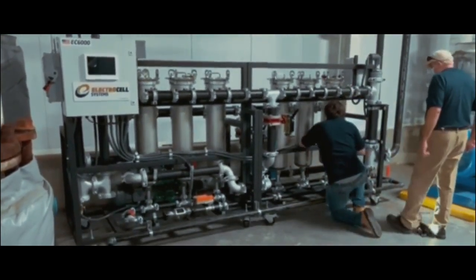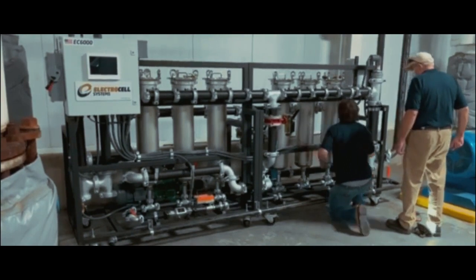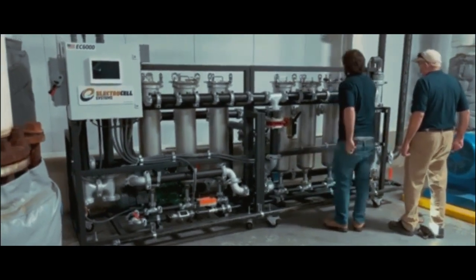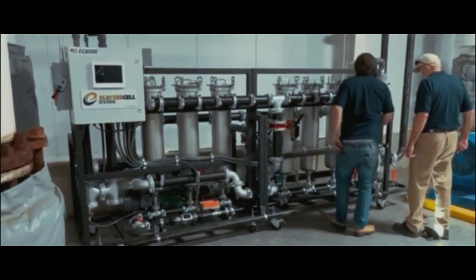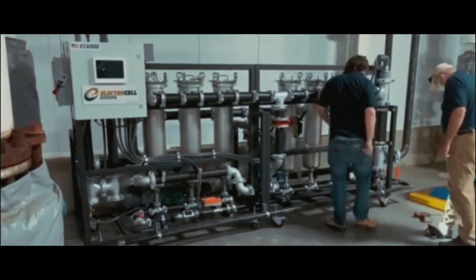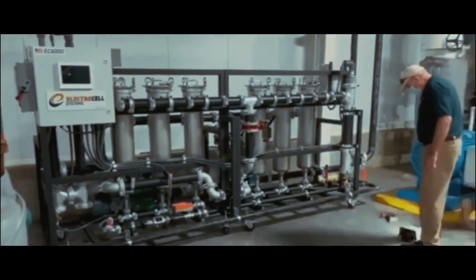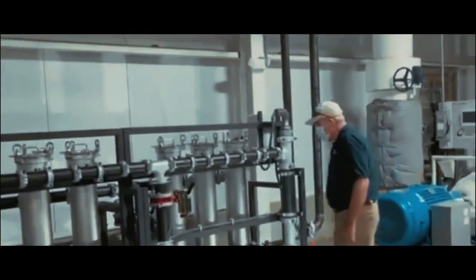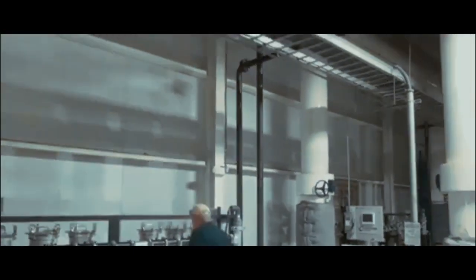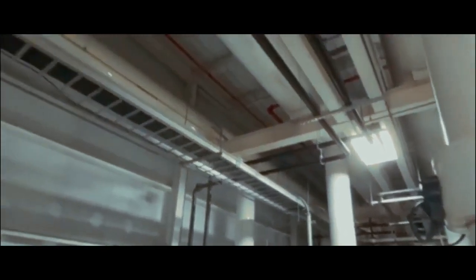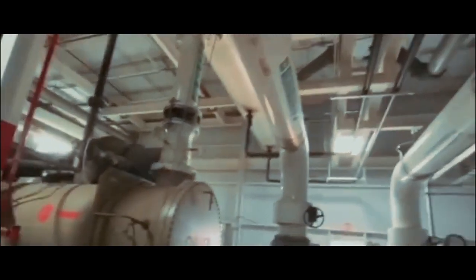ElectroCell's side stream operation allows for water treatment at a slower pace. This way, about 1% of the mainstream water will be treated at a time, with all of it treated over a 24-hour period. As you can see here, hot taps have been created into the main water flow, with smaller pipes now in place to allow water to flow properly through the side stream.